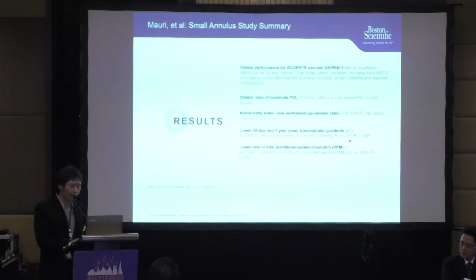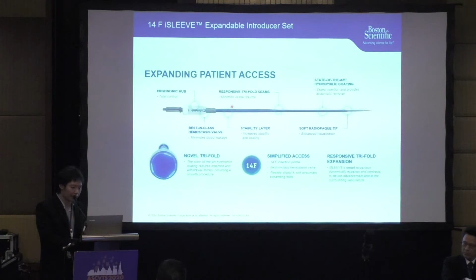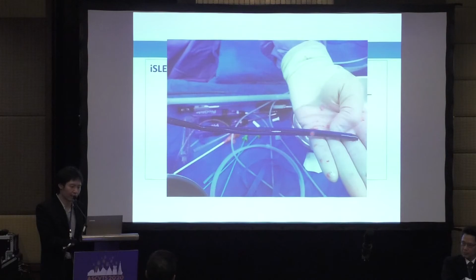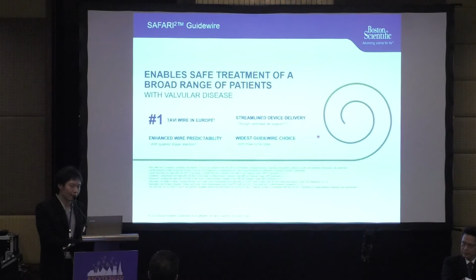So Boston company also provides a lot of accessory devices to perform TAVI. In this case, we choose to use a 14 French iSleeve vascular access. After the device is put inside, the 14 French iSleeve will be expanded in a trifold manner. So an iliac artery caliber of only 5.5 millimeters allows use of this sheath. After putting the device in the sheath, it will expand into a trifold. And they also provide the SAFARI guide wire. So this is the number 1 TAVI wire in Europe.